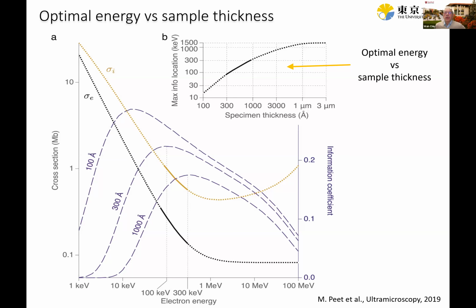So I have a question. When you operate the cold field emission gun, how long can you operate without doing anything to keep it clean? It's between 6 and 8 hours. I typically do the flushing of the gun when the cryogen refuel cycle starts. The microscope refuels the nitrogen every 8 hours or so, and I do the flushing of the field emission gun at the same time to avoid interruptions of the acquisition in between. And it drops the intensity? The intensity drops by about 10% typically. It depends on the microscope.